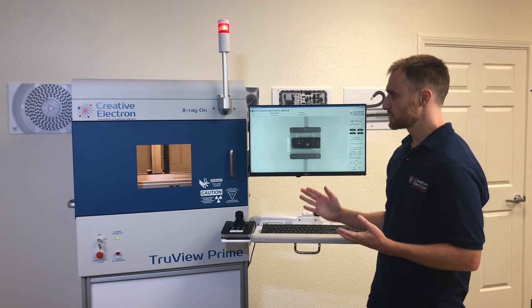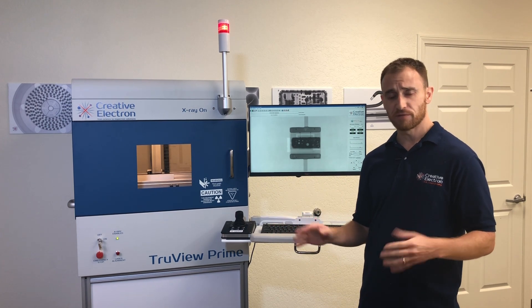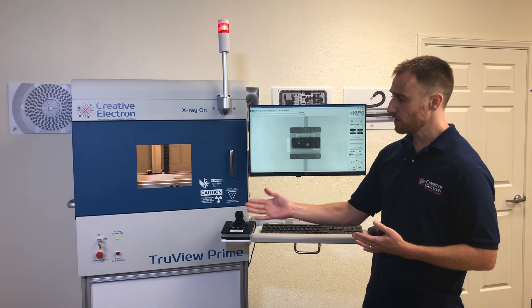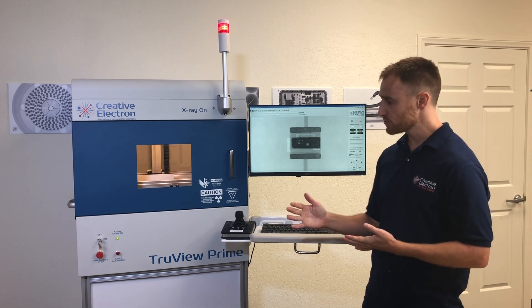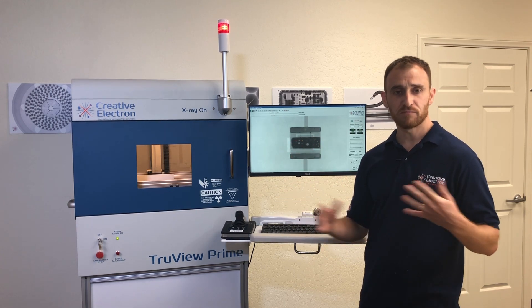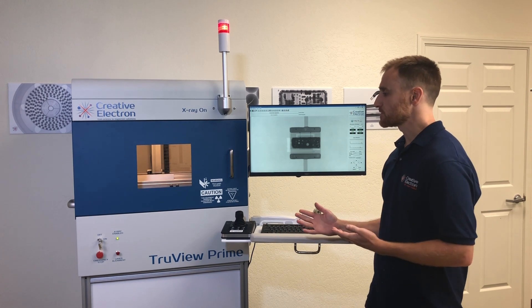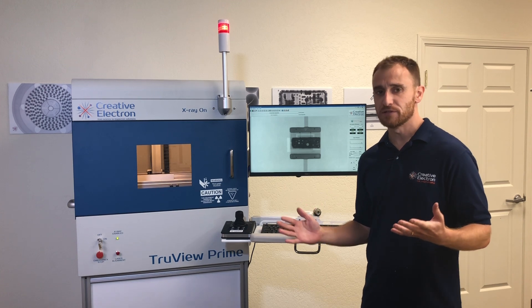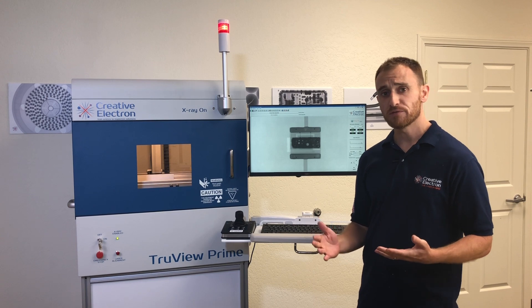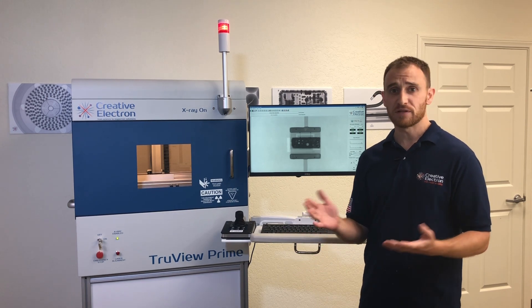The TruView Prime is compliant with all safety regulations worldwide, so you can use it anywhere and feel safe, because of the redundant interlocks, the key lockout, the emergency stop, the tower light, and just the construction that prevents any incident radiation from escaping the system. The customers that use this system are in every single NDT market, whether it's electronics manufacturing, automotive, medical devices, securities, and even defense corporations.